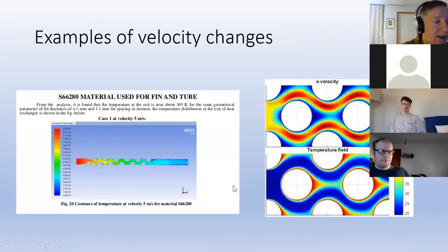These are examples of velocity change. There's indicators of velocity and temperature. The velocity increases as a function of geometry. You see behind the holes that the velocity is lower. When we look at pressure drag and fluid dynamics, that comes into play. You can think of these eddies behind tubes. There's these low velocity eddies behind them, and that causes a higher drag than you might think. If you look at temperature, behind the tube the temperature is higher, and that's because the velocity is low. Low velocity means poor convective heat transfer, and therefore the temperature is higher.